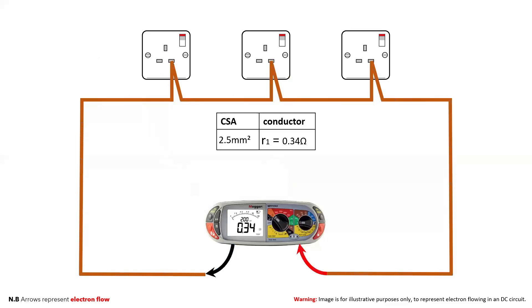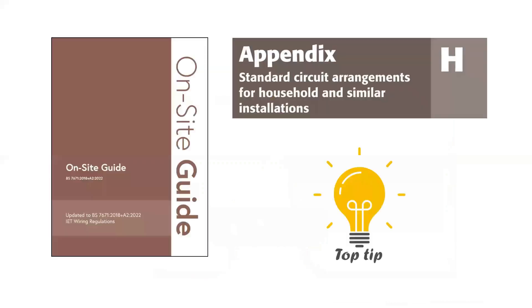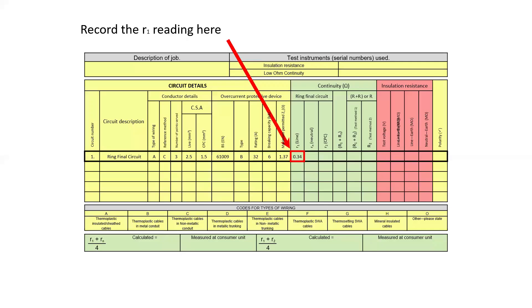As you can see we've got a reading of 0.34 ohms on the MFT. For the purpose of this video we are going to say that our line conductor is 2.5 millimeters squared as it would be in a standard ring final circuit up to 100 meters squared. Appendix H in the on-site guide gives more information on this along with table H 2.1. We can then record the reading of 0.34 onto the schedule of test results in the column for the line conductor little r1.